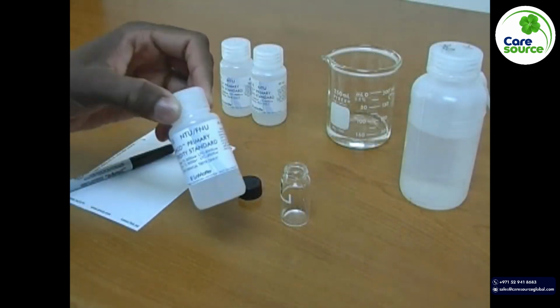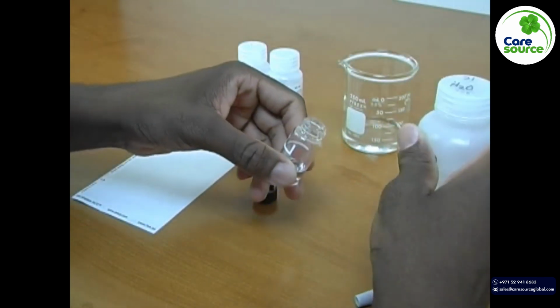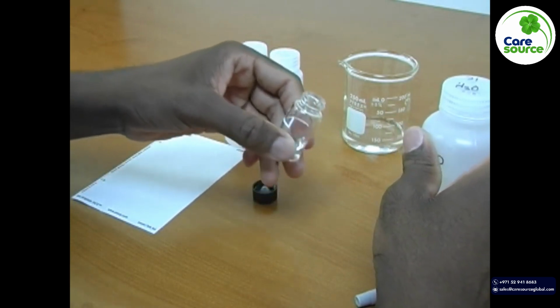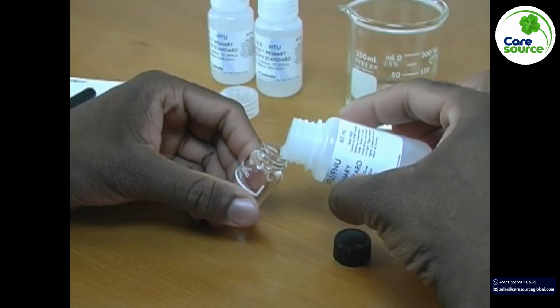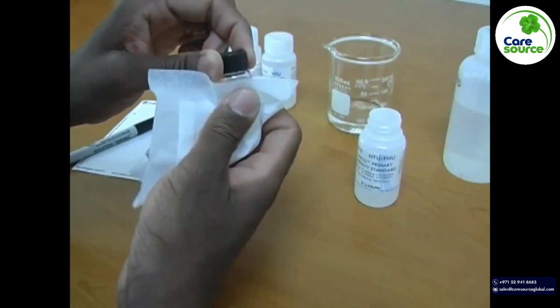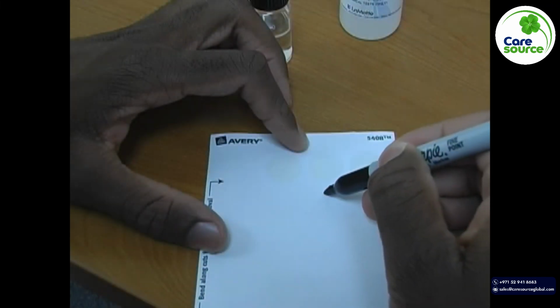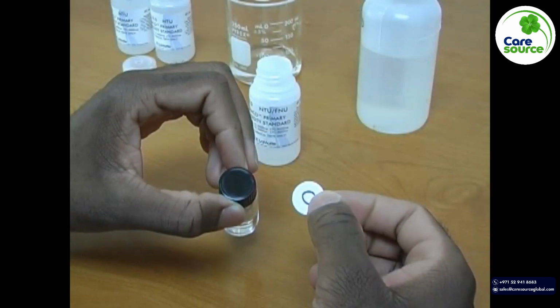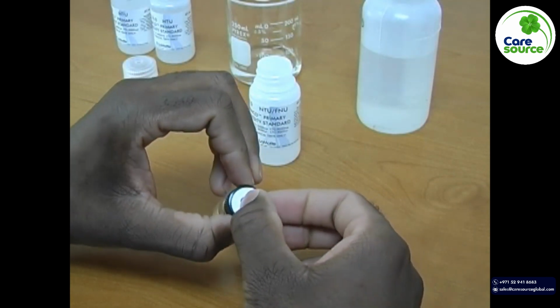Begin by inverting the standard, rinse sample tube, fill tube with 0 NTU. Dry the tube. On the labels provided, write 0 for the 0 NTU standard or the standard value used and place the label on the top of the tube.